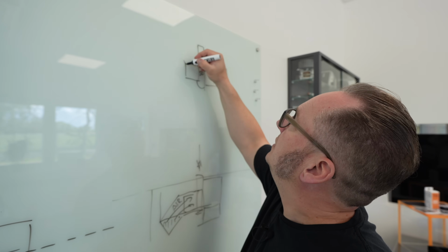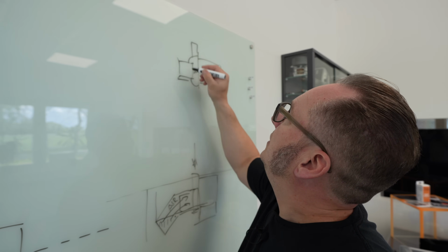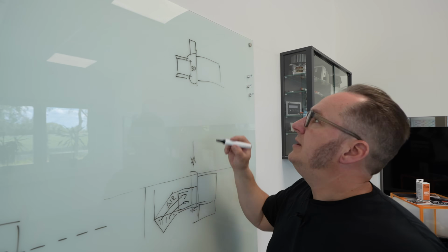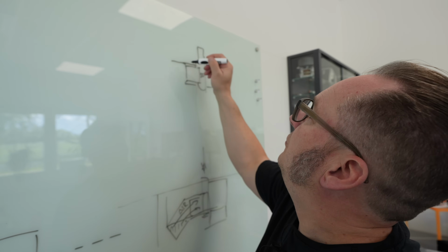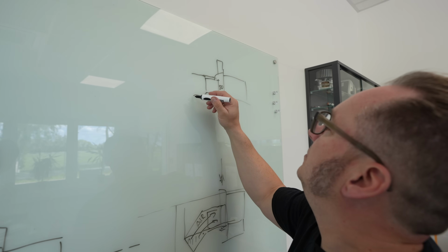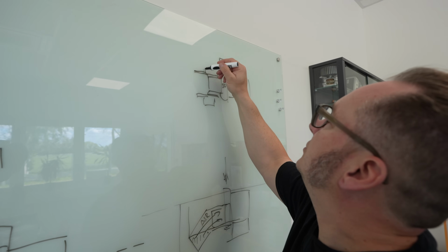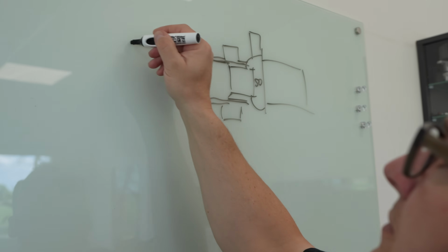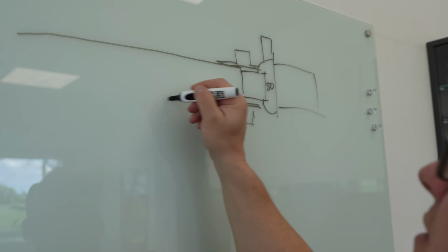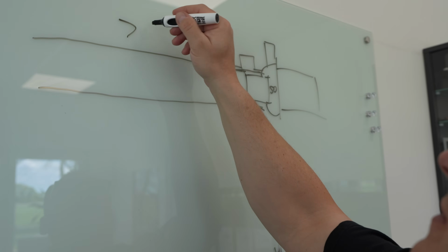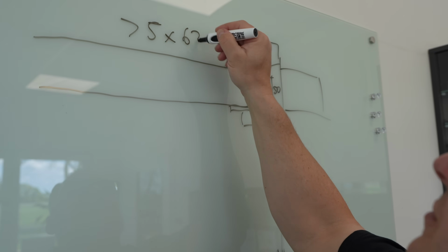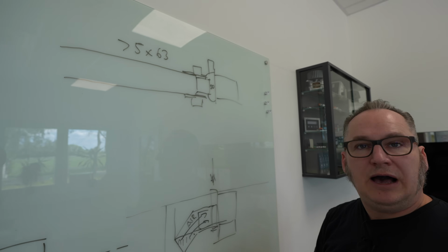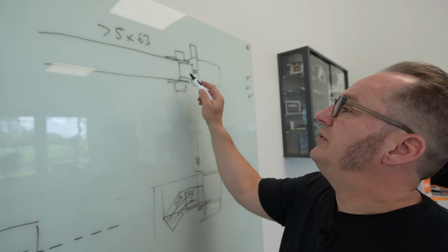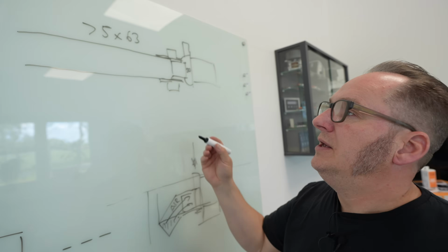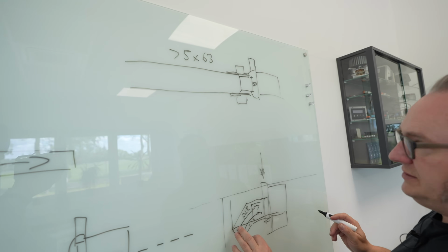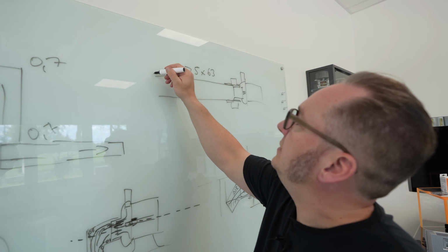What you should do is use a short reduction to go from 50 to 63. Then you place your fitting on top of that, which will be a bulkhead, so you can take that off. Then you have your 63 millimeter pipe, and this part should be at least 5 times 63. So 5 times the outer diameter of the pipe you should have as a straight run in front of the pump.